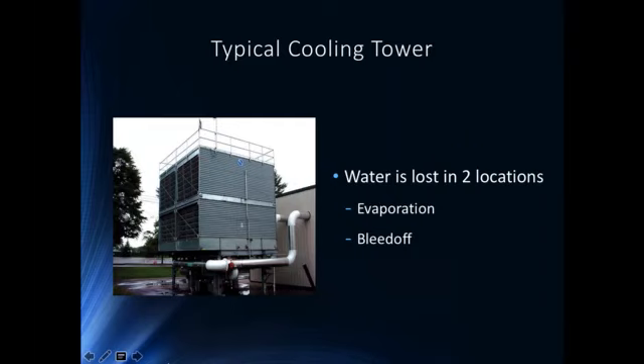Again, for those of you that don't see them all the time, this is an example of a cooling tower, and essentially water is lost through the cooling tower in two ways. The first way is through the top of the cooling tower, water is evaporated, and this is essentially how your heat load leaves the building. This is the last step in removing heat from the building, therefore keeping the tenants cool. And that water evaporates out the top. And so a lot of times on a cooler day in Southern California, as you're driving around the city, you can see what looks to be fog or plumes that are coming off these cooling towers. That's because that's water that's being evaporated out of it.